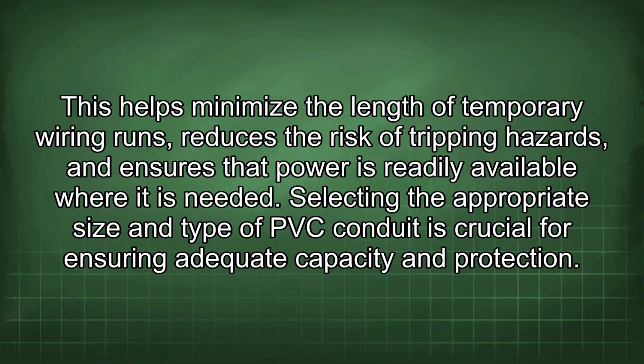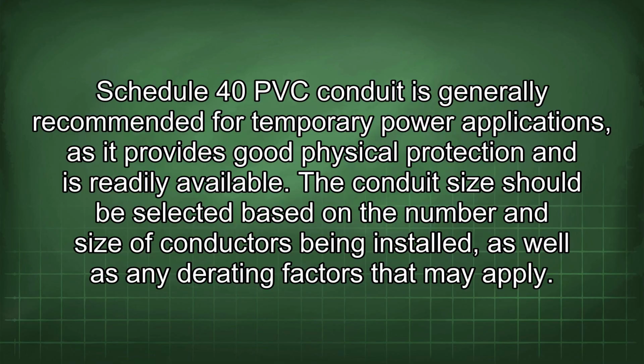Selecting the appropriate size and type of PVC conduit is crucial for ensuring adequate capacity and protection. Schedule 40 PVC conduit is generally recommended for temporary power applications, as it provides good physical protection and is readily available. The conduit size should be selected based on the number and size of conductors being installed, as well as any derating factors that may apply.